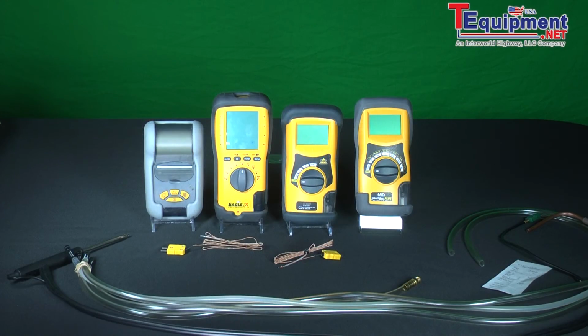Today we're here to talk about combustion analyzers or flue gas analyzers. These are used to measure the efficiency and safety of any combustion appliance. Combustion appliance is anything that burns a fuel, whether it be a wood stove, a furnace, a boiler, a range, a water heater, whatever the case may be. Whenever you're burning a fuel, you need to check it for safety and for efficiency.